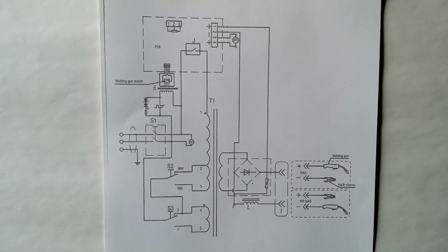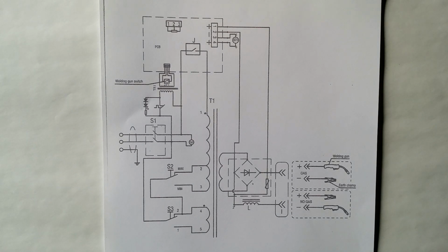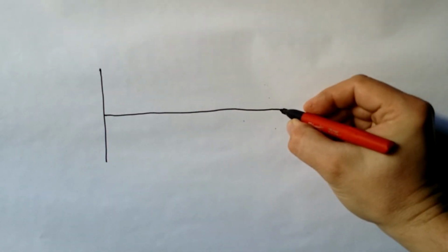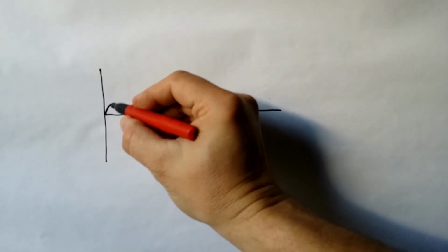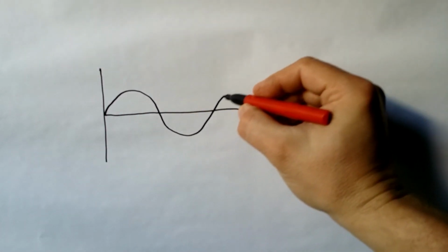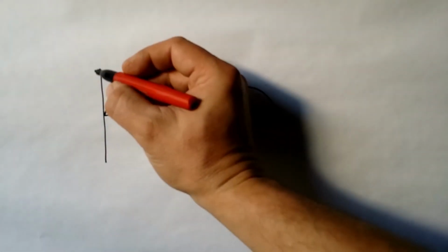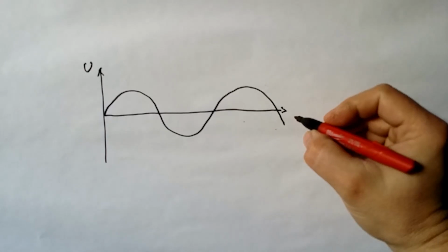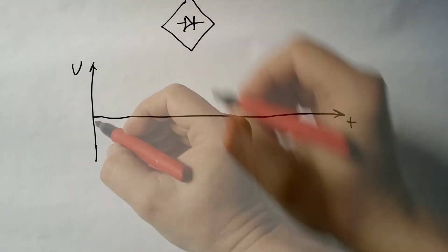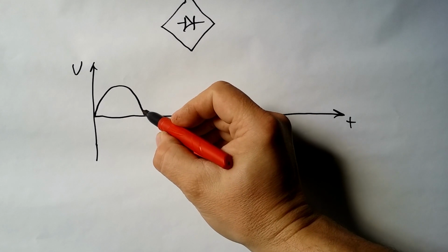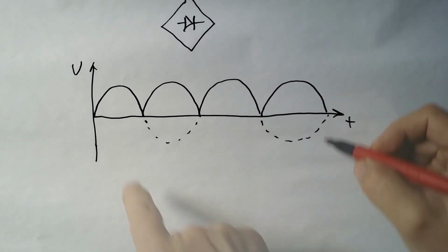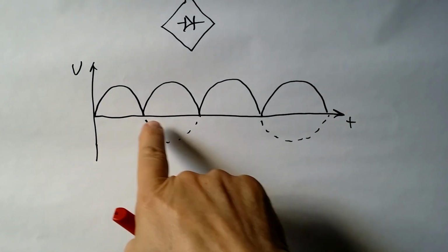Why do we have the rectifier and the choke? Transformer works only with AC current. If we didn't have the rectifier and the choke, we would have AC sinusoidal current. Our electric arc would light up and extinguish with the frequency of 60 Hz. We would love to have a nice and stable electric arc. The rectifier is not enough. It will just flip the bottom wave up. The arc will still go down to zero and up again.